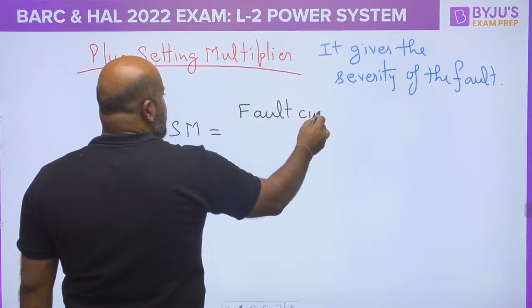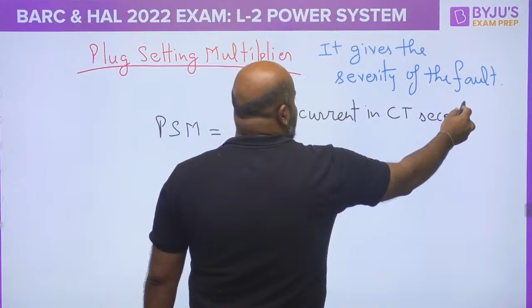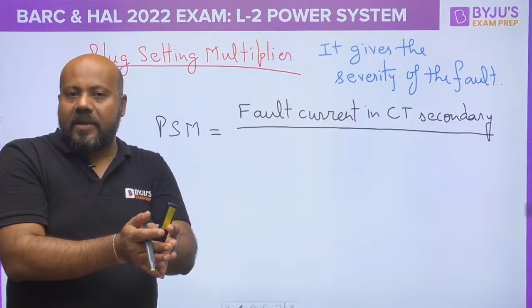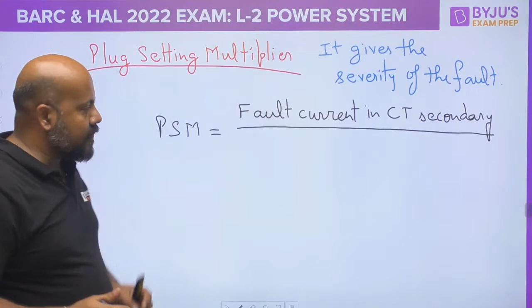See, what is my reference value when I talk about faults? When I talk about the relay operation, my reference value is the pickup value. The more the current exceeds the pickup value, the more dangerous the fault is going to be, yes or no? Suppose the pickup current is 5 ampere. If you are getting a fault current of 5.1 ampere, then it is going to be a fault. But if you are getting a fault current of 20-50 ampere and the pickup current is 5 ampere, it means the fault severity is very, very high.